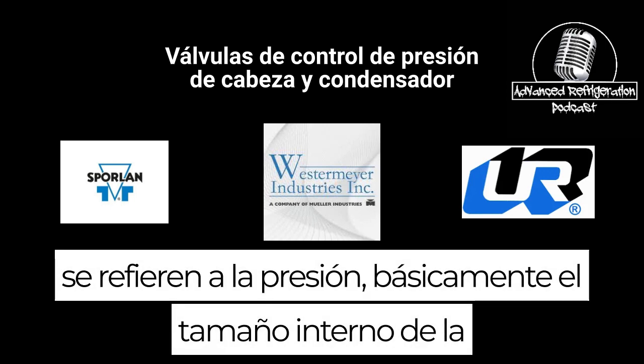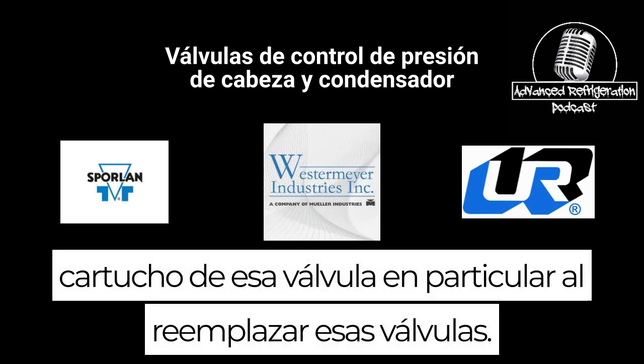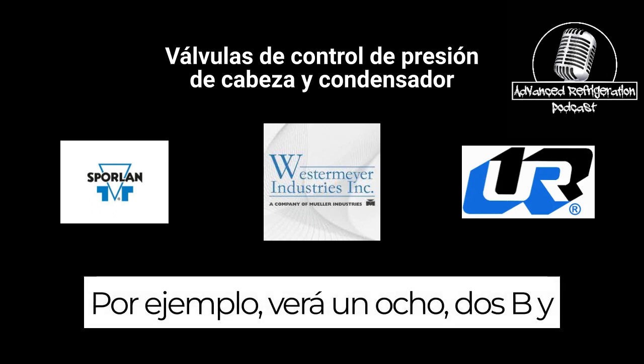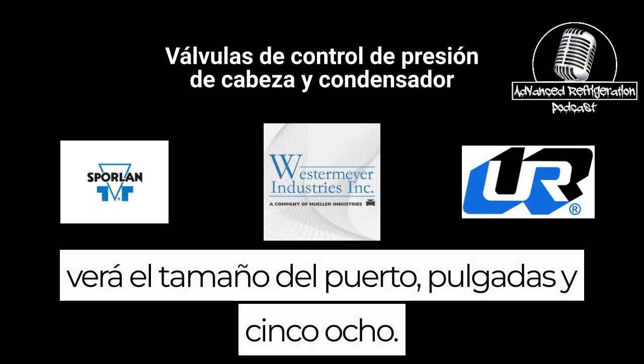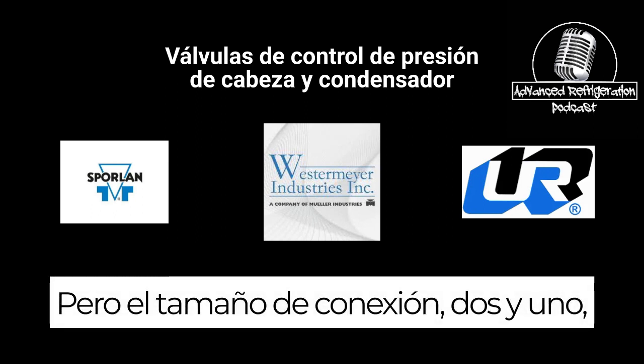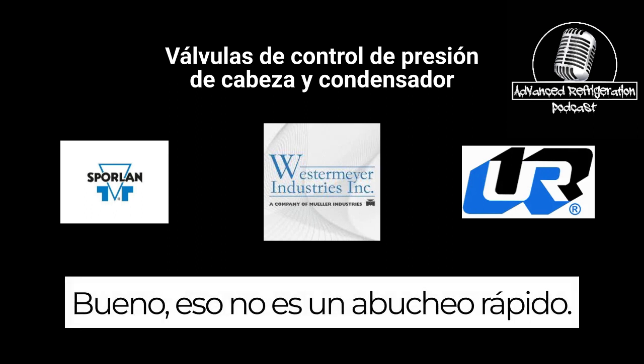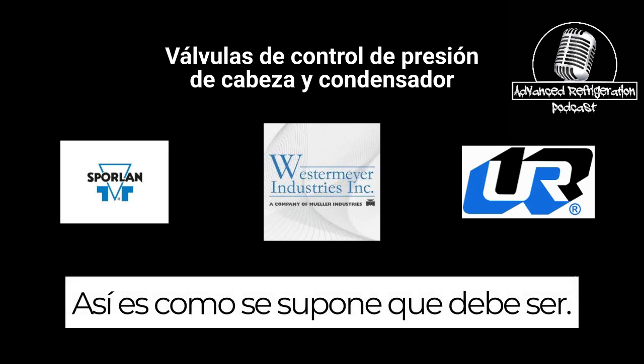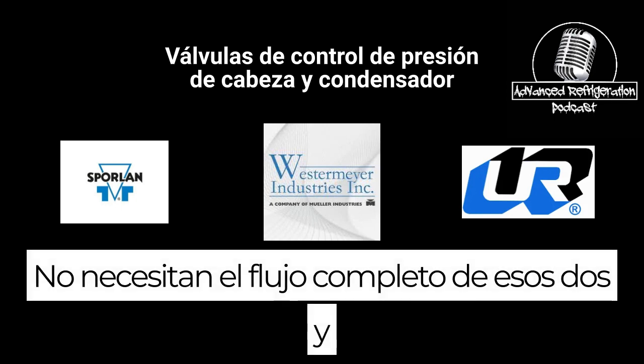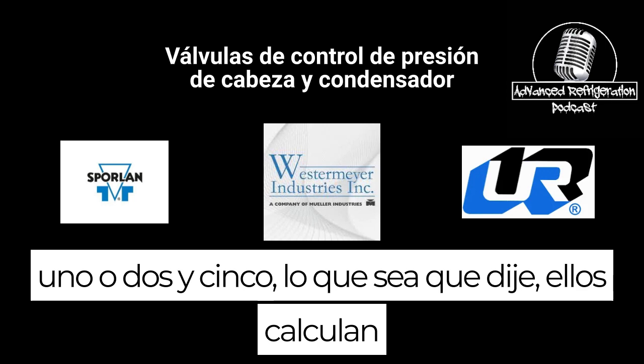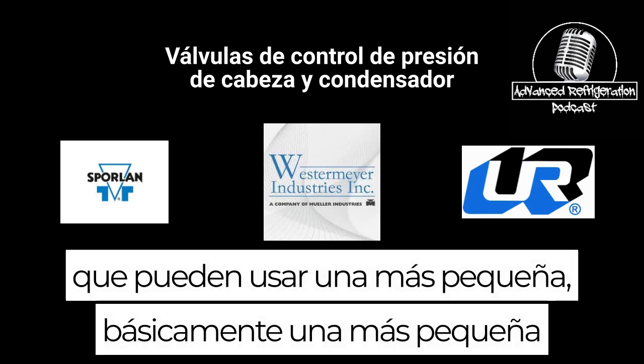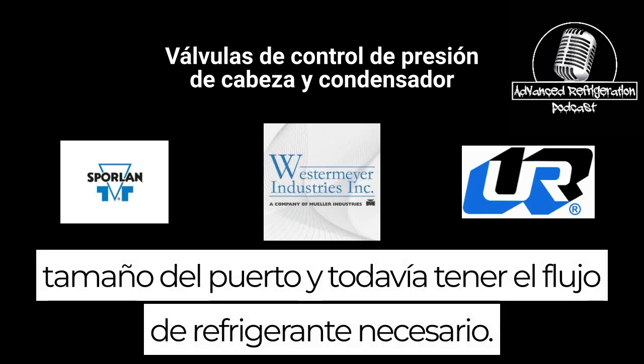When you refer to the port size, that's basically the inner size of the cartridge of that particular valve. When replacing those valves, for instance, you'll see A8, 2B, and you'll see port size 1 5/8, but the connection size 2 1/8. Well, that's not a snafu. That's the way it's supposed to be. They don't need the full flow of that 2 1/8 or 2 5/8, whatever I said. They figured out that they can use a smaller port size and still have the refrigerant flow needed.